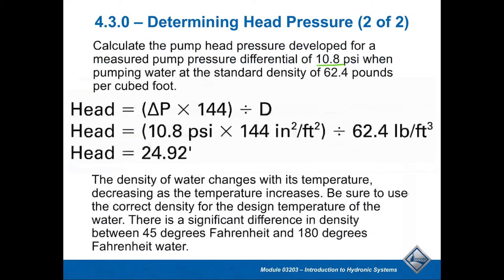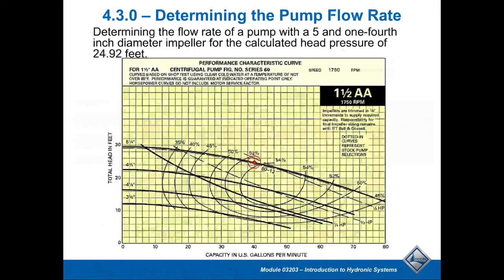For example, if a pump has a differential of 10.8 PSI across the suction and discharge, and we're pumping water at the standard density of 62.4 pounds per cubic foot, we take 10.8 × 144 ÷ 62.4 to get a head of about 24.92 feet. The beauty of this calculation is that if we warm up water, the density decreases as molecules expand and don't weigh as much per cubic foot — so we can correct for that.